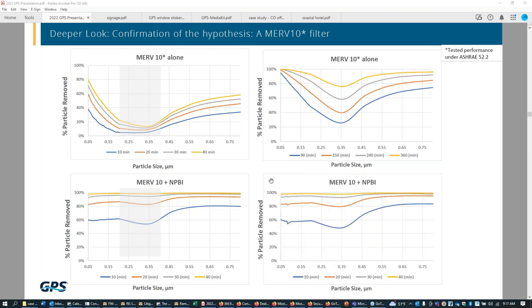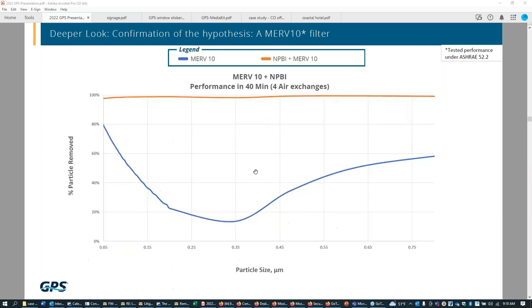And we've done this repeatedly in the lab, and found that the curves hold true after multiple runs. And we see this in the field. As a field salesperson and engineer, it's very nice to see in the lab, where we can control all the variables, that we can demonstrate repeatably what we often see in the field. This is the summary shot showing in blue a MERV 10 filter by itself after 40 minutes with four air changes, compared to a MERV 10 filter plus ionization with the same protocol.